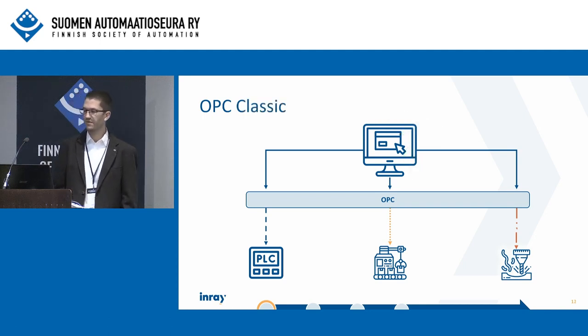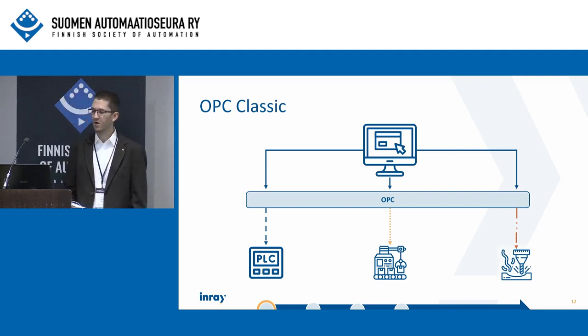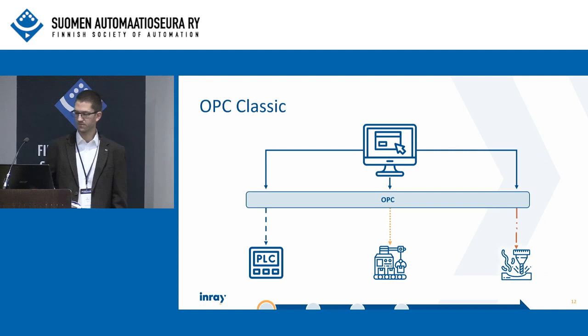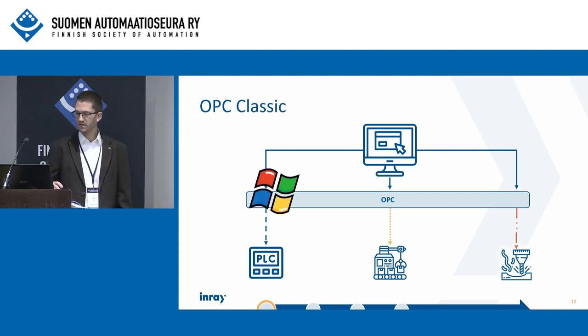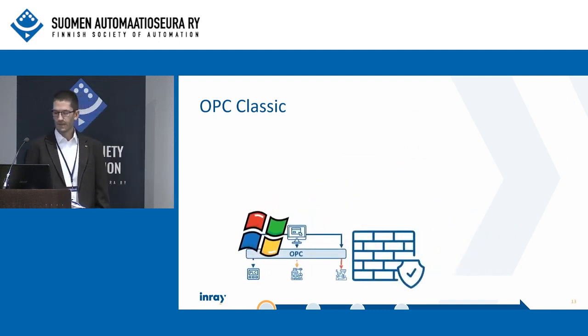However, not everything about the first version of the OPC standard, today also called OPC Classic, is perfect. It relies massively on Windows technologies and does not allow complex data types or semantic models. Especially the foundation based on Windows COM is an enormous challenge in practice.